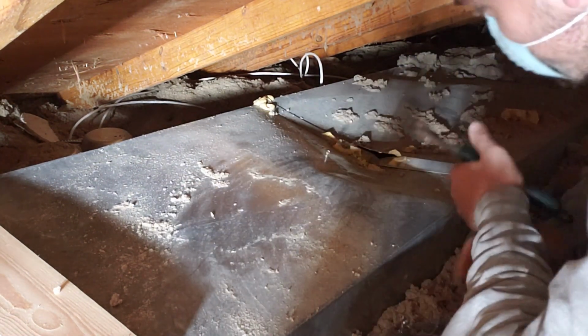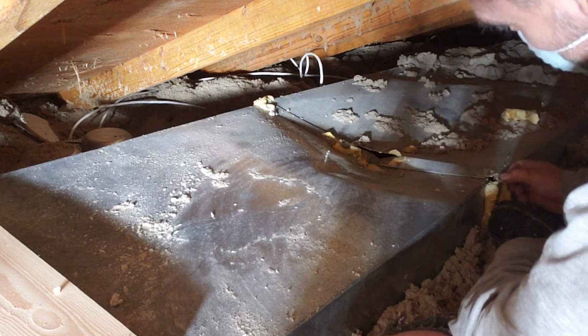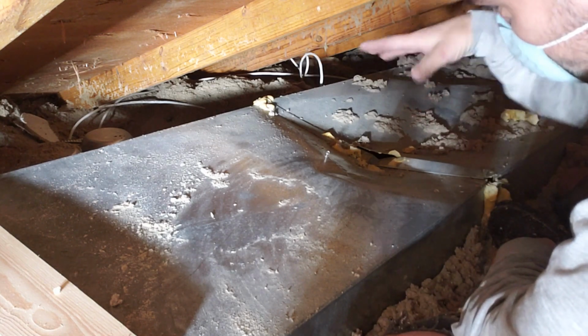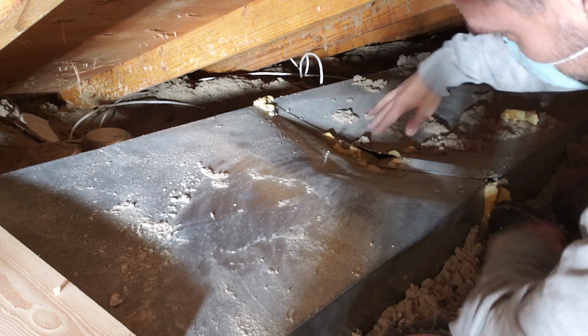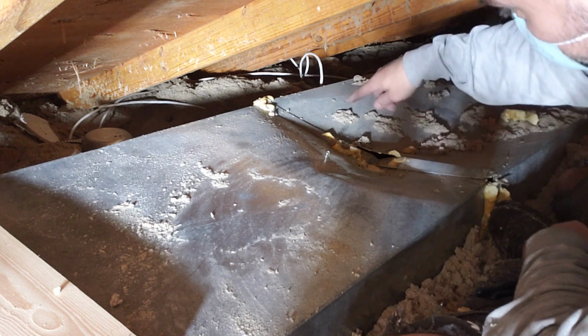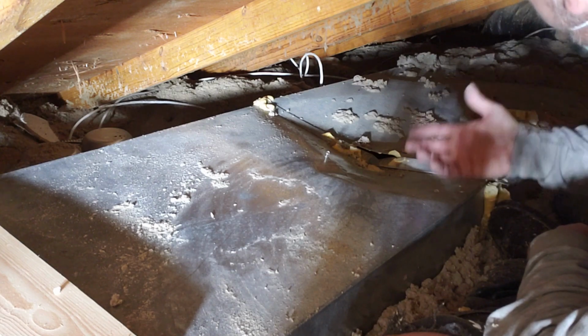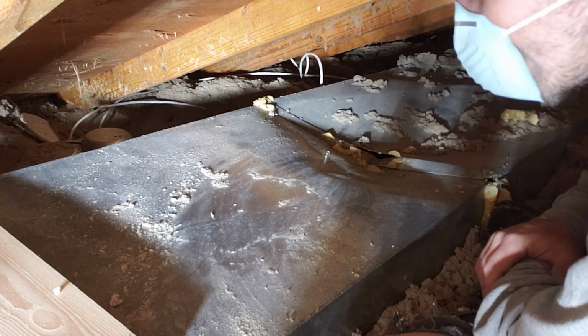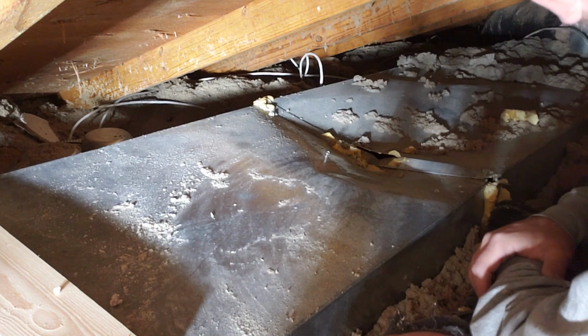Interestingly, they had to have climbed in here at some point and saw this all caved in, and there were a couple of gaps because it had bent. There was a big gap right here and then on the corners, and they spray foamed it shut. But the duct was completely collapsed, so I don't know how any airflow was even getting past anything here. Unbelievable.